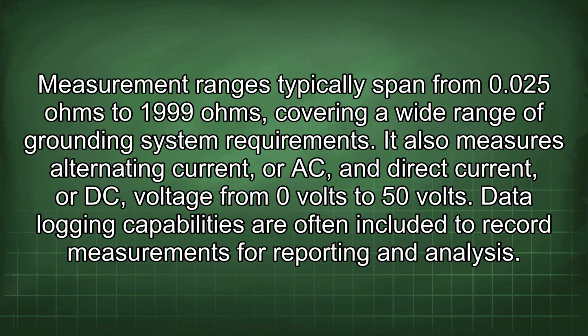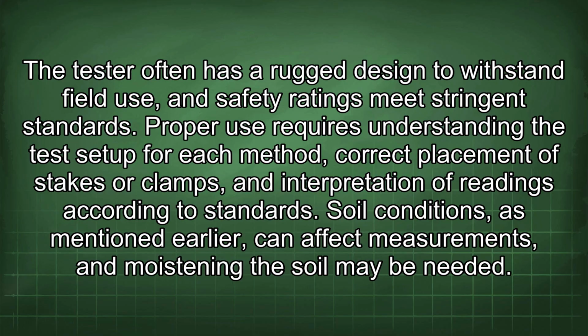Measurement ranges typically span from 0.025 ohms to 1999 ohms, covering a wide range of grounding system requirements. It also measures alternating current, or AC, and direct current, or DC, voltage from 0 volts to 50 volts. Data logging capabilities are often included to record measurements for reporting and analysis. The tester often has a rugged design to withstand field use, and safety ratings meet stringent standards.